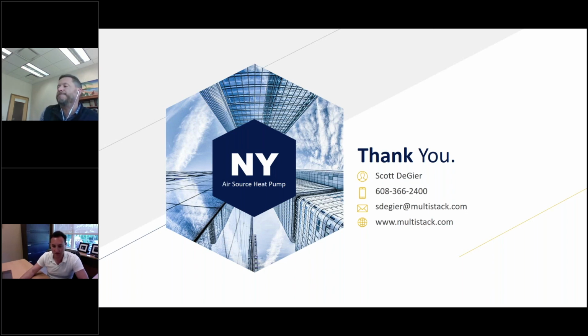Okay, great. Is the 10-degree delta T between entering and leaving water typically the best practice for optimizing plant efficiencies for heat recovery chillers? I would say 10 degrees is the example I gave. I would say it really comes down to overall plant design, but I would tend to lean closer to 10 than to 30. So if you had somewhere between 10 and 15 degrees, that's probably the optimal spot for the equipment and for the system. But again, depending on what the actual system looks like, that could vary. But yeah, I think that's a good target.